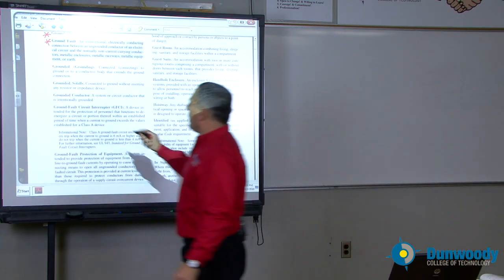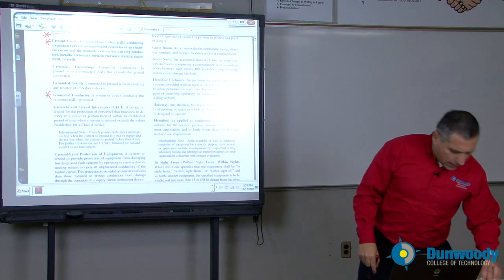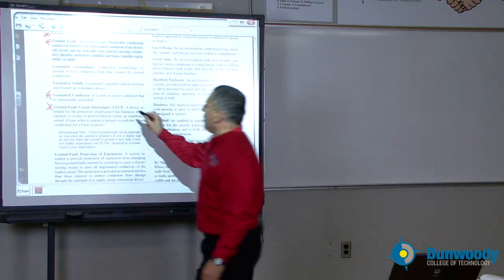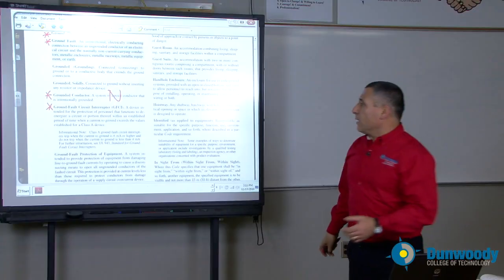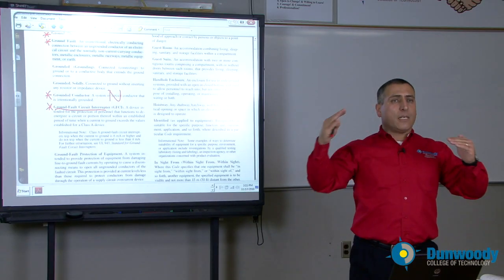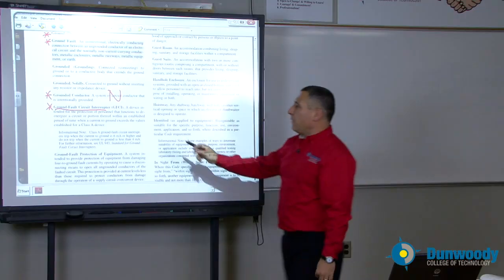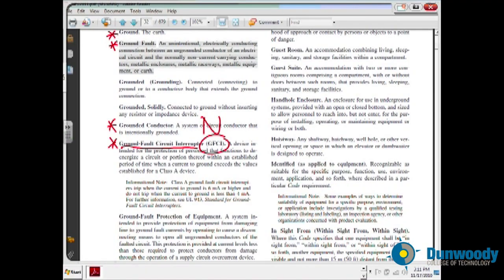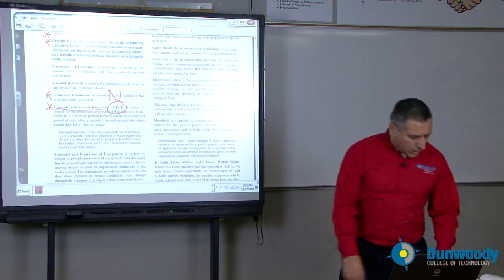Grounded conductor — this is my neutral, my neutral conductor. Everything in the code is defined by the ground. We have the ungrounded conductors — these are the hots: phase A, phase B, phase C. Grounded conductor — these are the neutral. Grounding conductor — that's the ground. Ground fault circuit interrupter is a specially designed piece of equipment that monitors the current going through the hot and the neutral and trips. Very important to understand the definition of GFCI — we need GFCI in the kitchen, GFCI outside.